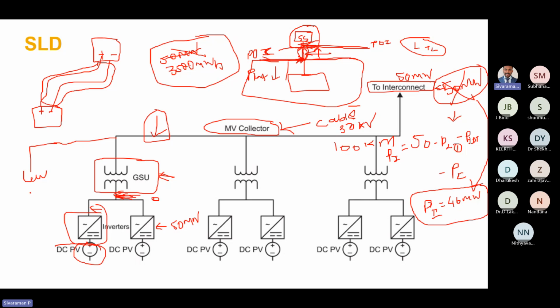So we have to install the solar inverter, and its DC panel capacity shall be more than 4 megawatt, because there will be some losses associated at this point. So we have to install one more block whose power rating is 4 megawatt, a little bit higher, right? These are some of the design aspects we have to consider for designing any solar PV system.